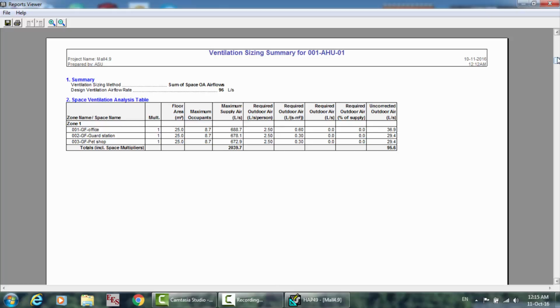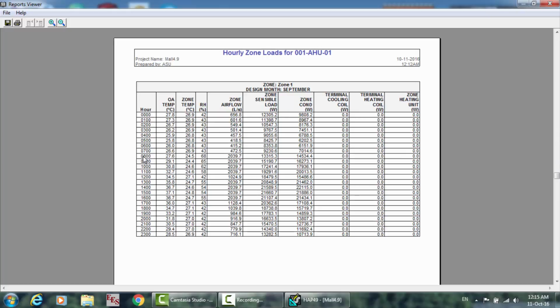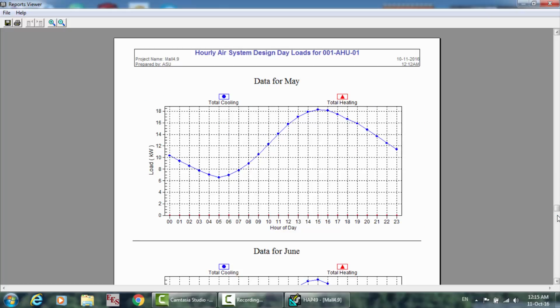In the last versions, I think HAP only shows from 8 to 12, and then from the specified hour, not all the hours. Here is the data for May. You can see from 0 to 23, but it only takes from 8 to 12, and then there is a break according to our schedule. It will be according to our schedule to 17 or 18, and this is the cooling load from here to here, not all this period.